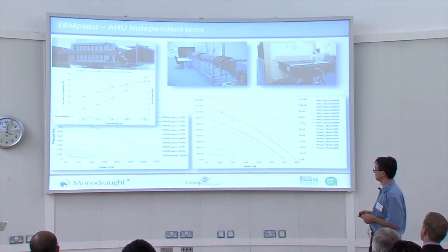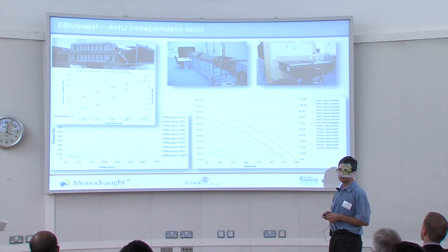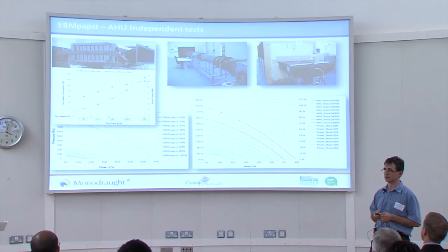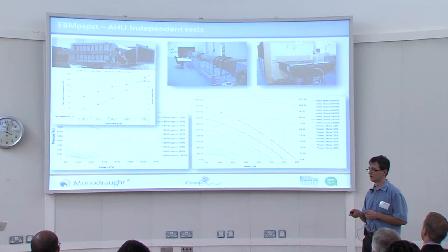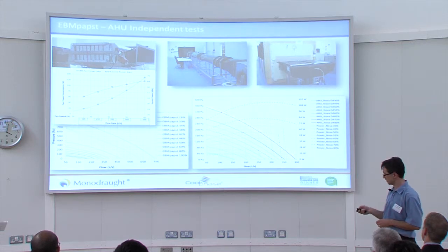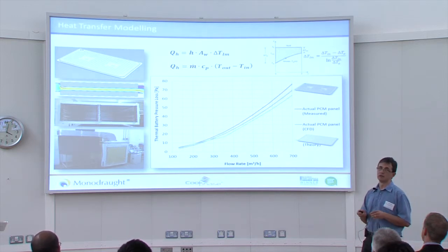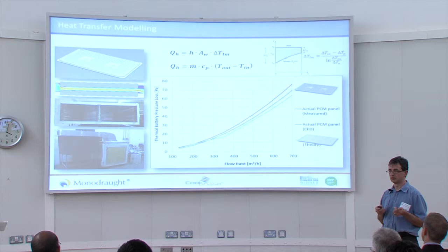Okay, well, we did a fair bit of testing and modeling. First of all, we had to make sure that our air handling unit is operating as we expect. So we're not just using an efficient fan, but the envelope of the fan has to be also efficient, so as to get the least loss. Then we were carrying out testing, CFD calculation, and analytical calculation.